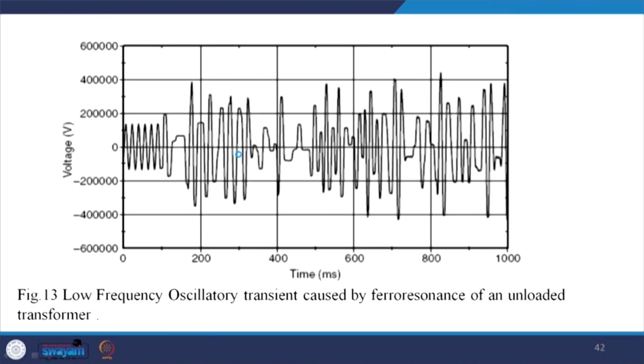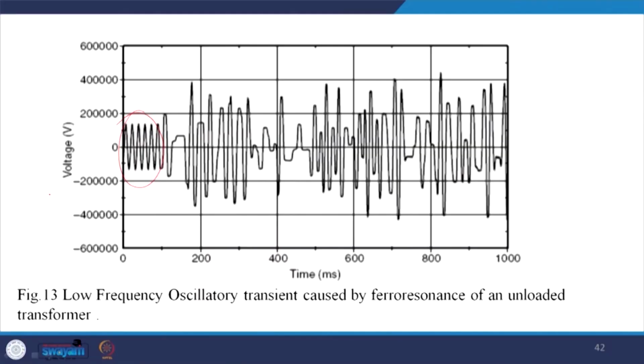Now, this is an example of an oscillatory transient caused by ferroresonance of an unloaded transformer. We may have a leakage reactance, thereafter it can interact with the capacitor bank and may have a resonance at a particular frequency. Maybe you got a resonance at the 7th harmonic, which may be generated by the adjustable speed drive. It was okay, and all of a sudden you got ferroresonance and a 7th harmonic oscillation. This kind of phenomenon can also be seen in the case of ferroresonance of an unloaded transformer.